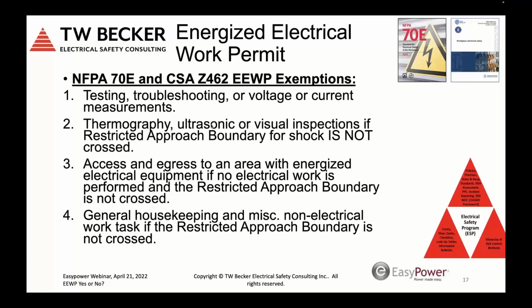So these are the 4 exemptions. 3 says access and egress to an area with energized electrical equipment if no electrical work is performed and the restricted approach boundary is not crossed. So I can go into an electrical room and I don't need a permit. And I don't even need arc flash and shock PPE to go into the electrical room, if I'm just going in to, again, read panel meters, right, inspect the room visually, right, inspect the electrical equipment externally, right, without opening it up. So we don't need a permit to go into an electrical room.